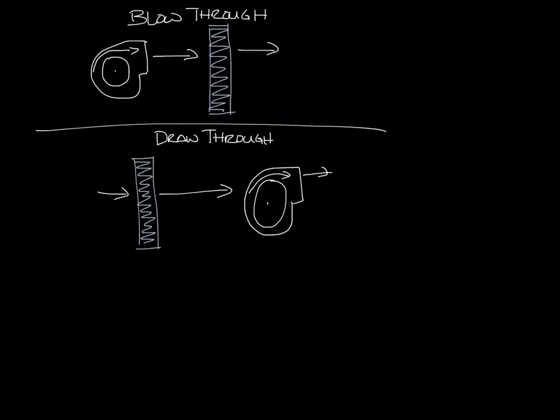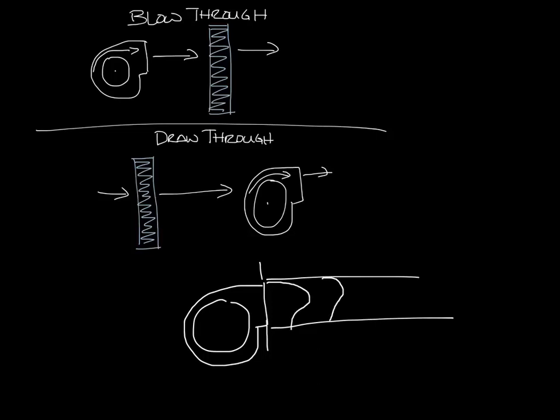Let me make a little bit of room and let's just look at a fan maybe it's mounted to a discharge panel and connected to some ductwork. So the velocity profile coming out of the blower is going to kind of look like this where at the top of the blower where the air is coming it's got a higher velocity and as it moves down the ductwork it eventually evens out into a more uniform flow.